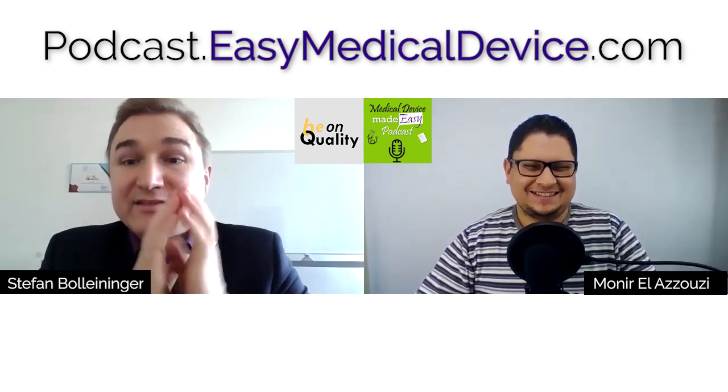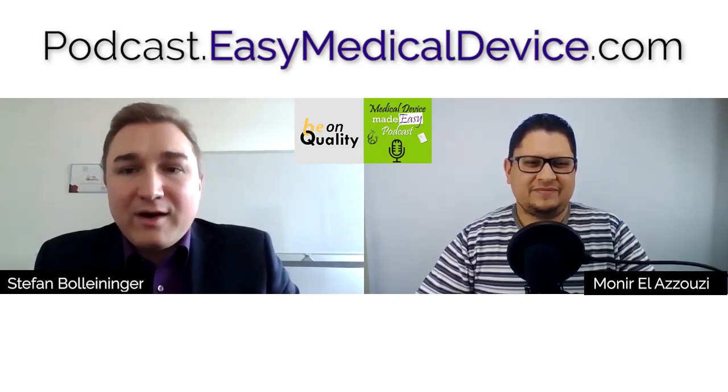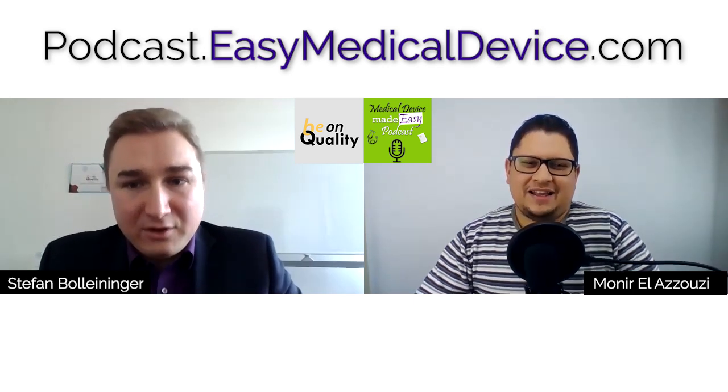Quality management is a journey. The auditor improves, you improve. And so you have the non-conformity, look at it. Do I need an immediate reaction? Yes, no. Then decide, why do I need it? Why don't I need it? Rationalize it. Make a good, clear rationale of what you have done and what not. Then go and make a good root cause analysis and ask yourself, why did it happen? What has been done? Is it a direct or an indirect problem for the quality management system? And then go down with the 5 whys until you can answer the question, okay, now I know why it happened.